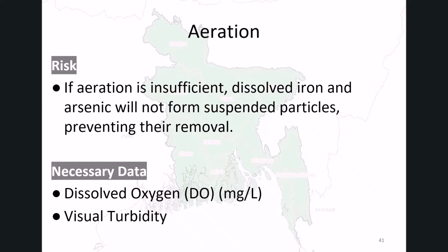To evaluate aeration performance, we check two key parameters. First, the dissolved oxygen, which should be above 4.0 milligrams per liter. And second, visual turbidity. After aeration, water should become slightly turbid as oxidation occurs.